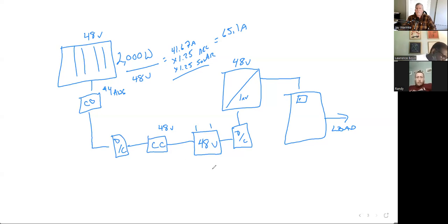I'm reading from column 1 because not only the wire has to be compatible, but the termination connections for both pieces of equipment. I don't know what they are, so I'm assuming the lowest temperature rating. We're always going to read from column 1 when designing these things. And 4-gauge wire is pretty expensive - probably about a buck a foot.